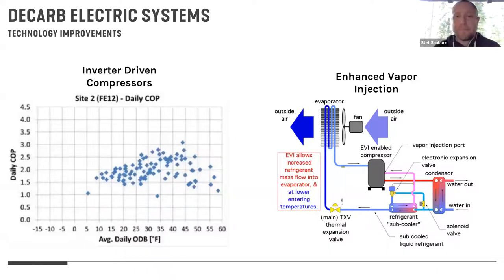The other reason why that's important besides that delta T is you're asking the compressor to do less work, so it's going to improve your performance of the system. So once that refrigerant is able to pick up that heat from outside, even though it's cold out, it goes into the compressor. And this is where the vapor injection is really important. The refrigerant that's coming off of my heat exchanger is re-injected about midstream into the compressor itself. And that heat that I pulled off of the refrigerant by subcooling it is acting to a certain extent as a form of compression, helping the compressor heat up that refrigerant before it goes back to your condenser coil.